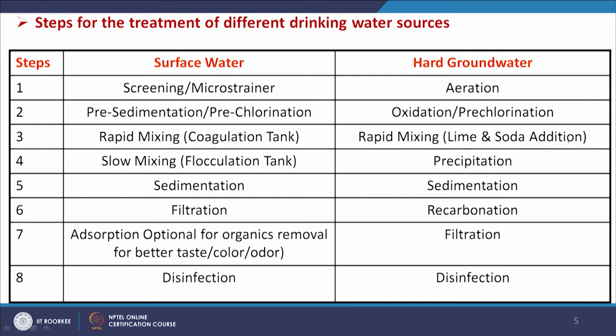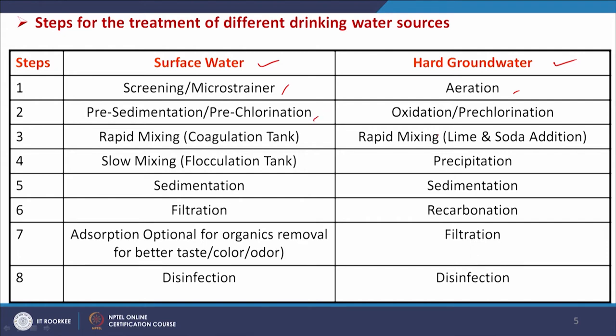Looking at the steps for treatment of different drinking water sources, surface water and hard ground water follow almost similar steps. For surface water, screening or micro straining is used, but for hard ground water this is not required. In some cases, aeration is required for ground water, because by providing oxygen some reduced forms of different ions can be converted to their oxidized form and removed more easily. Pre-sedimentation and pre-chlorination — or oxidation and pre-chlorination — are also needed for ground water to convert certain ions to their oxidized form for easier removal.